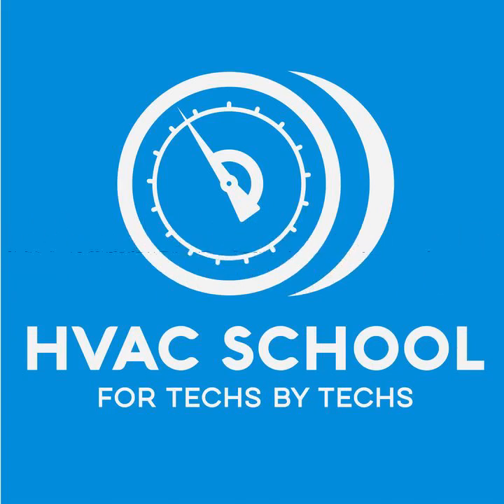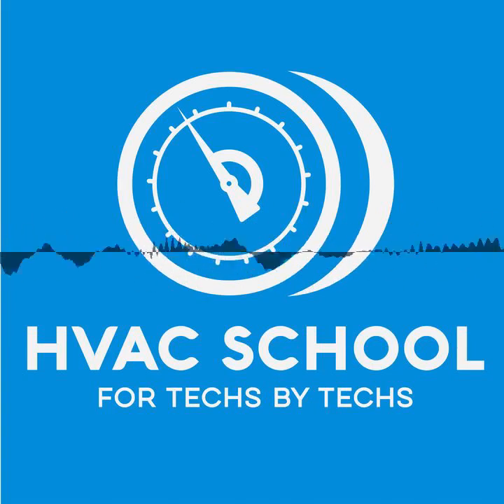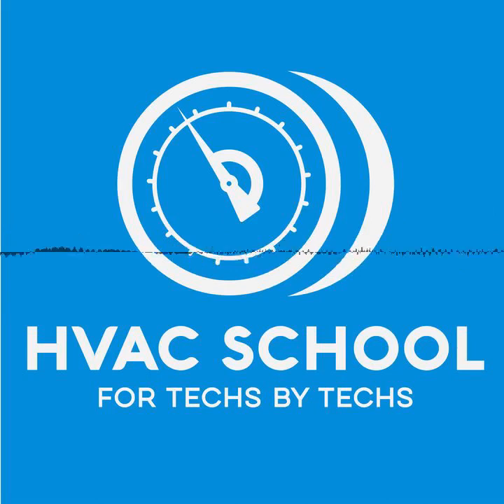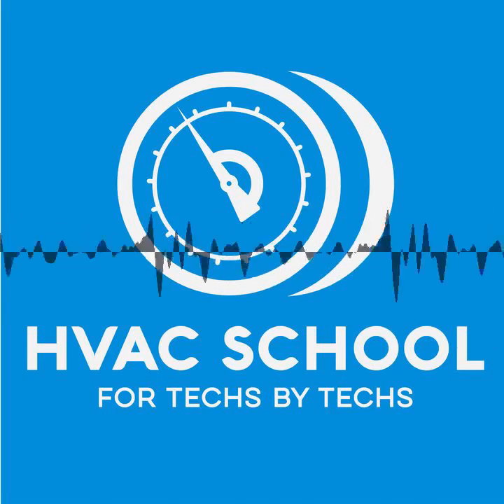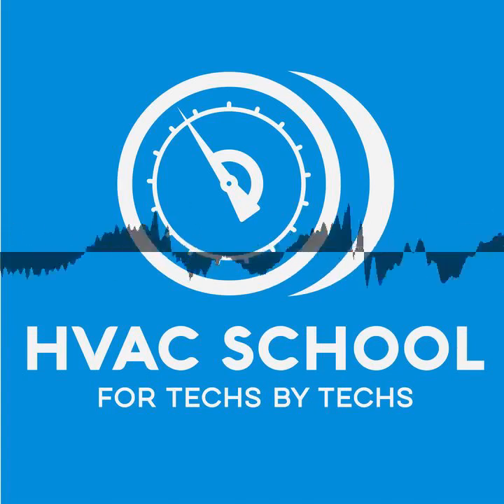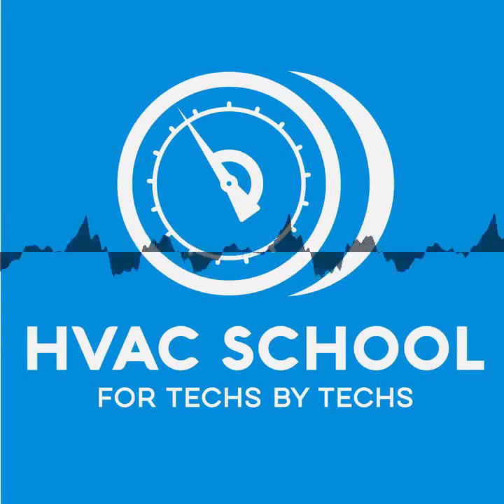When we valve it off, the leak rate is so low at that point, when it's down to 250 and we're letting it rise to 500, if it doesn't go above 500 in 10 minutes, the leak rate is so low that it's insignificant. It's just technically, it is leaking. And if you let it sit for 2 or 3 days or 2 or 3 weeks, you would see that your vacuum rose up over 1,000 or 2,000 microns at some point. Whatever it is, it's going to continue to decay, but what we're looking at is leak rate. Don't ever think that you can get a system so tight that you're not going to have a leak.